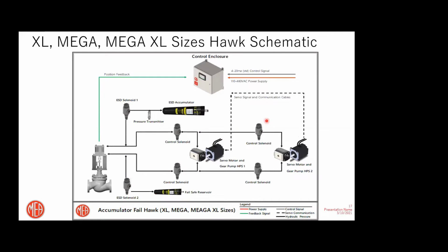So very flexible platforms. Additionally, you can equip this actuator with fail-safe accumulators or ESD accumulators, in which case, during a power up, you power up the unit and the unit goes through the recharge cycle. So we open these ESD solenoid valves, one for the accumulator, one for the fail-safe reservoir, and we take the fluid from this fail-safe reservoir and dump it into the accumulator. We charge the accumulator until the pressure transmitter is satisfied. Then whenever it's satisfied, we close the solenoid valves and the unit goes back into operation.